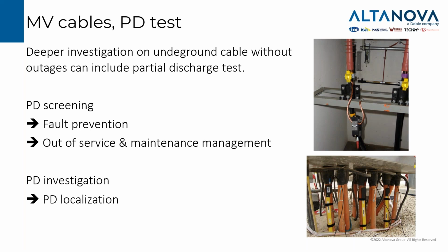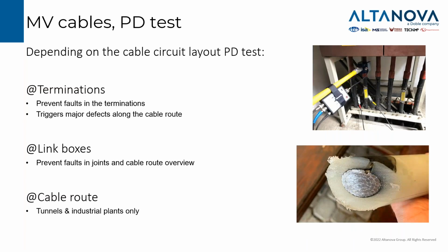It's not, let's say, so easy online because we have lower reflection properties of the media and we are working in a noisy environment, but in some lucky cases we can also localize exactly the partial discharge along our circuit. Depending on the layout of the medium voltage cables, we can perform a test at the access points that we have. So 95% of the time for medium voltage cables, the only accessible detection point will be from the cable termination sites. So we can be very effective in preventing faults in these terminations that we are testing.